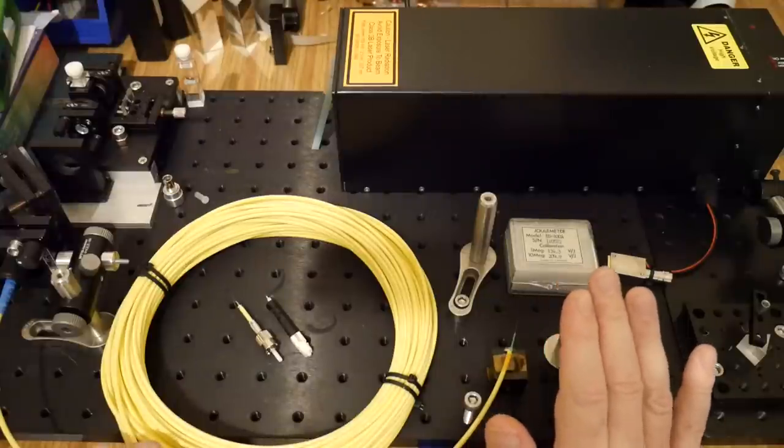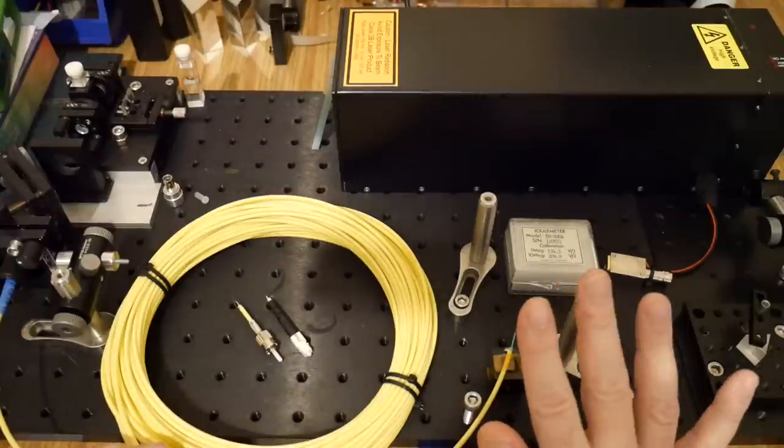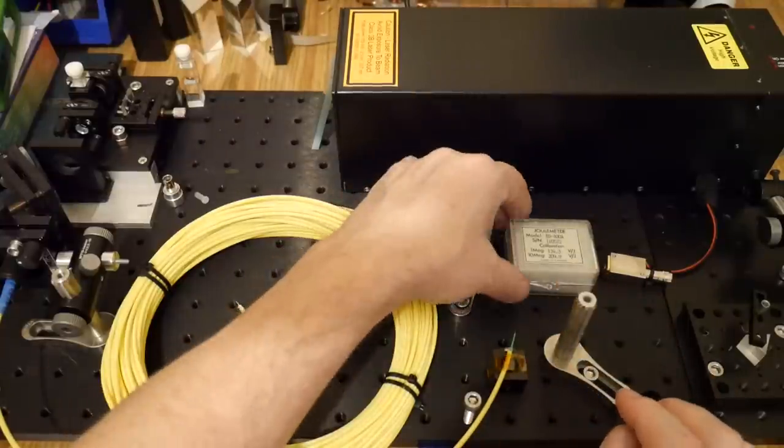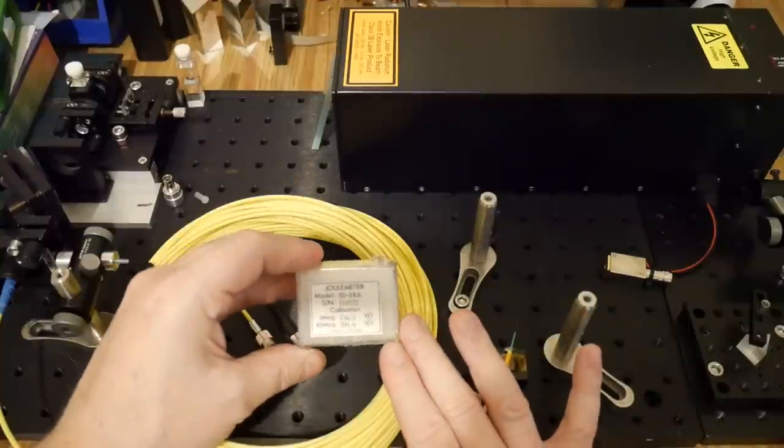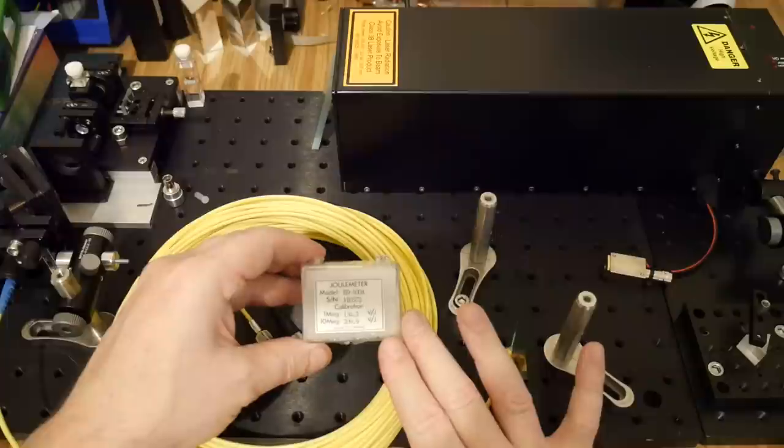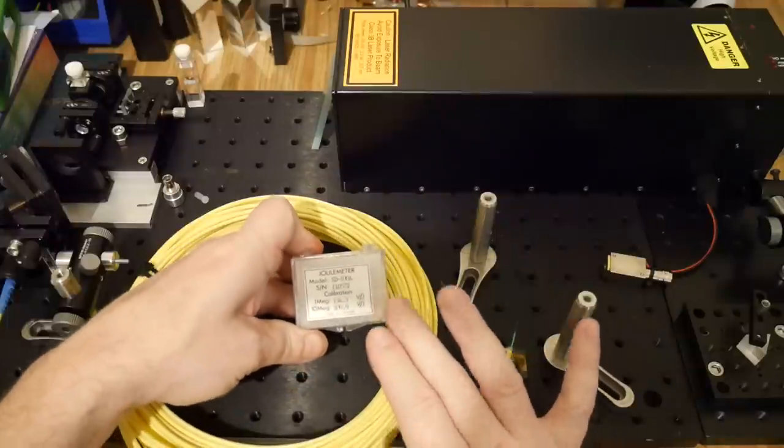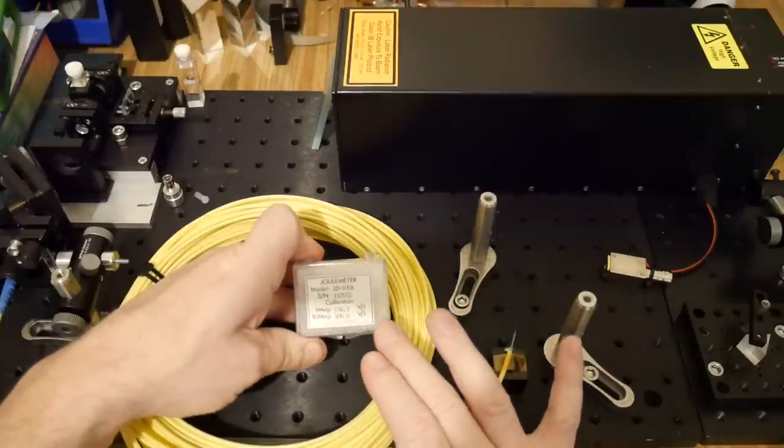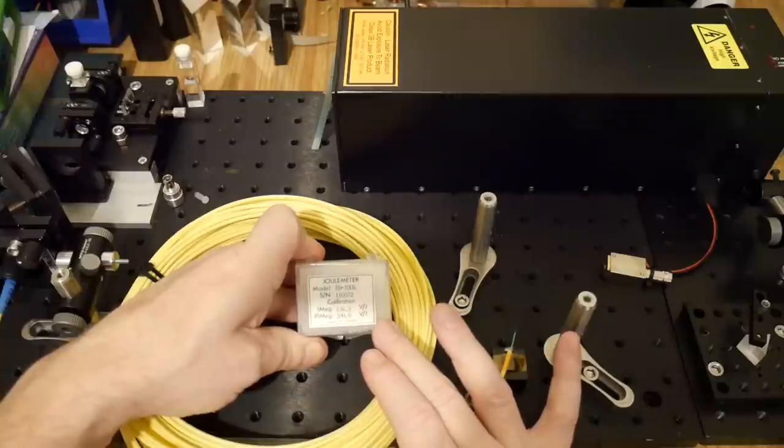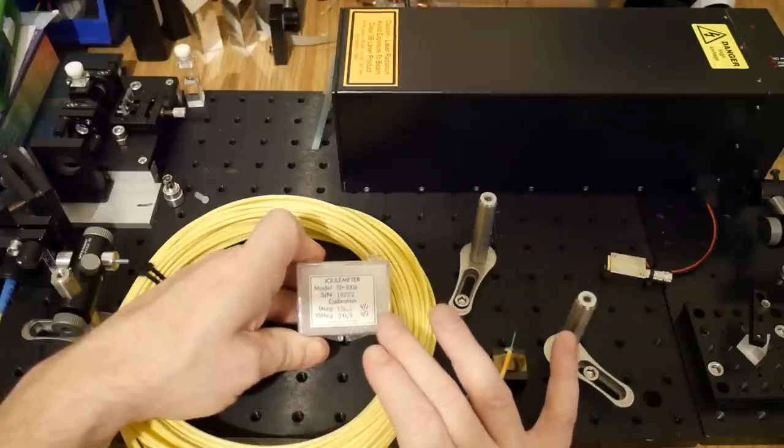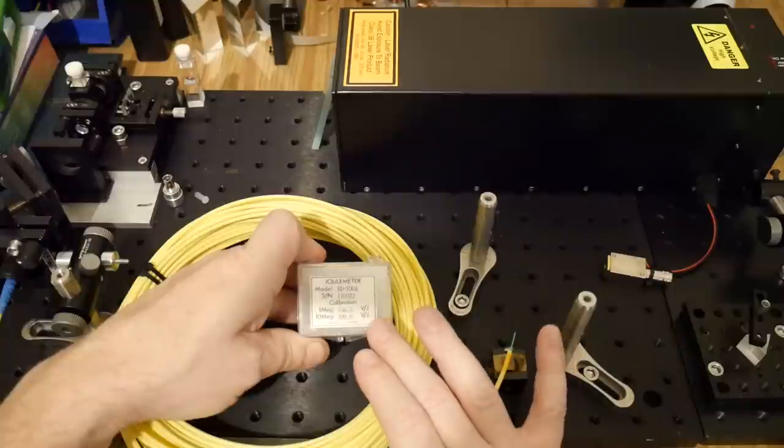In order to measure pulsed lasers like this we actually need two sensors to do the job. The first is a joule meter. This doesn't measure in the time domain at all, it just measures joules. The idea is we mount the sensor in this beam path and we actually read off a signal using an oscilloscope.